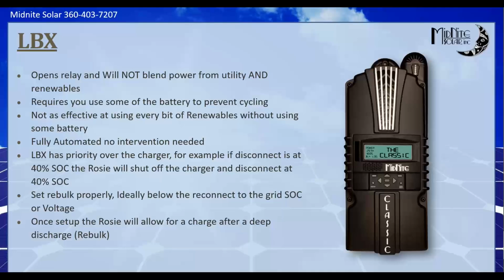But one thing to keep in mind is the LBX takes priority over the charger now. So with that in mind, if your charger is programmed, as you'll see here on the next page, we'll talk about it a little bit. But if the charger is programmed and you've got disconnect at 40%, reconnect at like 80%, let's say, then what's going to happen is when you hit 40%, the relay is going to close, the grid is going to be present, the Rosie's actually going to recharge the battery on you until it hits that 80% and disconnect again. So in LBX, you really do want to disable the charger, in my mind.